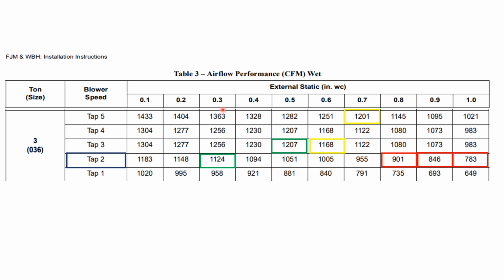Now, a lot of people will put the probe in the wrong spot. Like I said, I'm going to refer you to the podcast on static pressure. It'll show you where to put the probes. This is where ICP recommends probe placement on our equipment, so to test it.